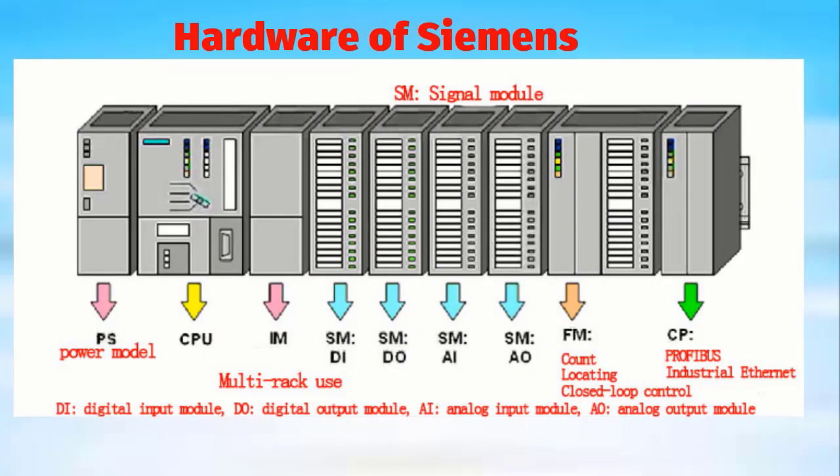The last topic of this lecture is the hardware of the Siemens PLC. The first module is the PS — the power supply module, which provides 24V supply to all the modules and the CPU. Next is the CPU itself. Then the IM — the interface module. Next is the DI — digital input, and DO — digital output. Then the AI — analog input, and AO — analog output. You can connect your input/output modules — digital or analog — according to your project and design.